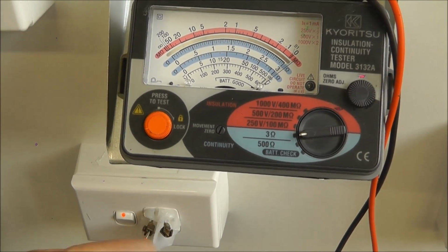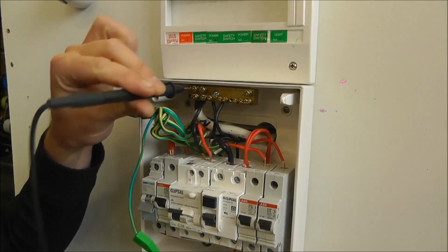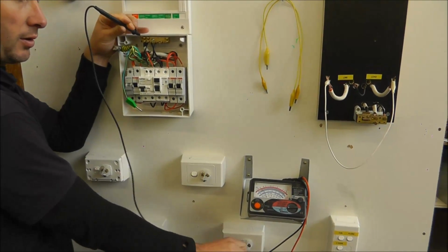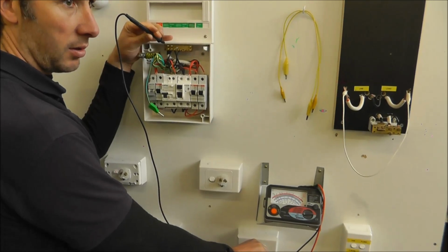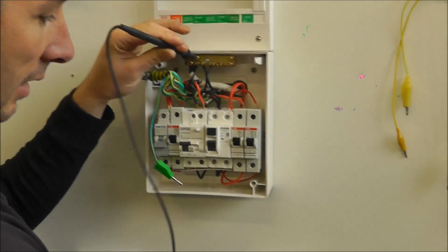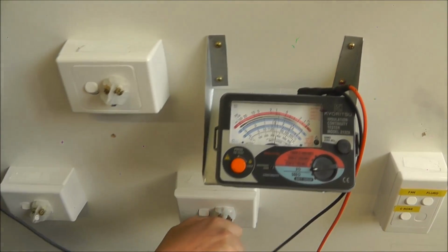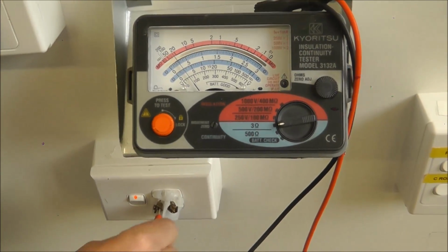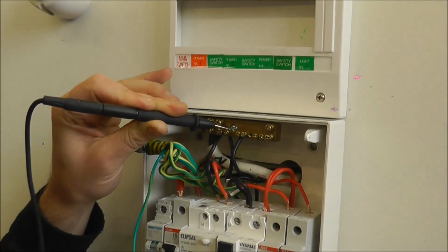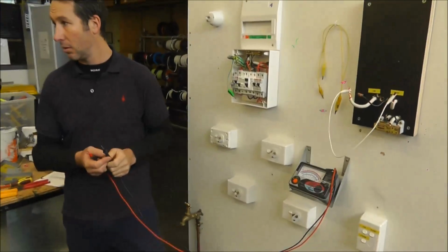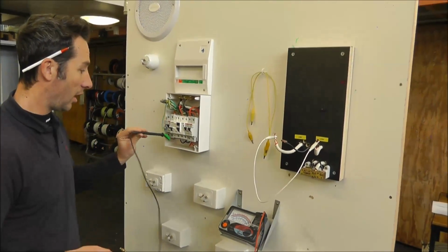So what am I going to do now then? I'll go to the neutral bar. Now, can I go up here? I can do that. Why? Because all the breakers are turned on. I don't care which circuit it's on. I just need to know that the neutrals all flow back to here. Look, the neutral's switched. So I'm in this terminal here, but up here I'm on the neutral bar, so the neutral's switched. Bad news. Yes?